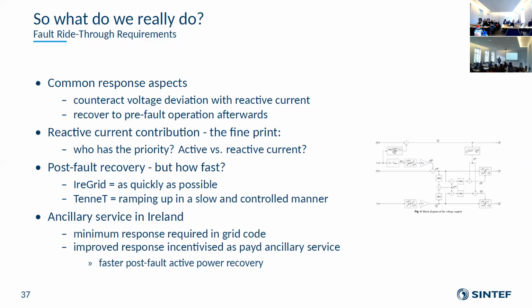There's also a big difference in recovery. In Ireland, they say you have to recover as fast as possible, while in TenneT, they say you should recover in a slow and nice way. But this slow recovery also means that if you don't want to change the pitch of the wind turbine, for a longer time you harvest energy which you are not allowed to push into the grid. So you need to go somewhere with that. This is also a non-heterogeneous picture.